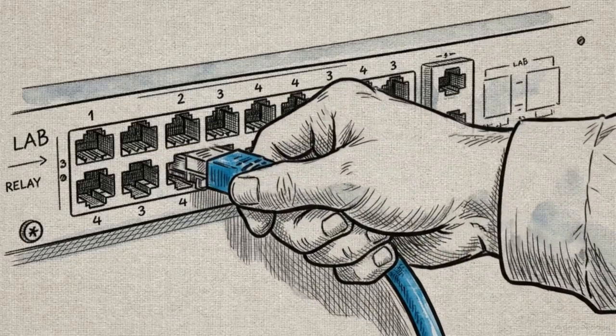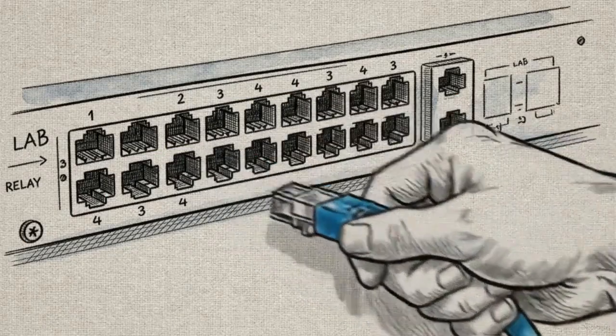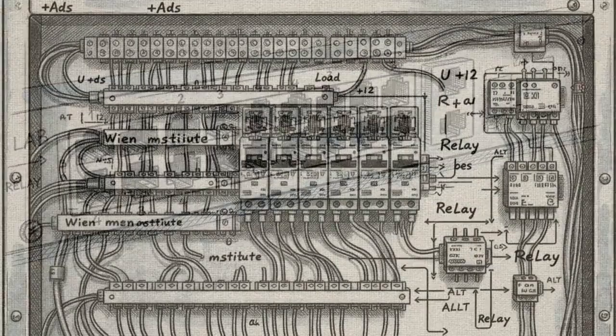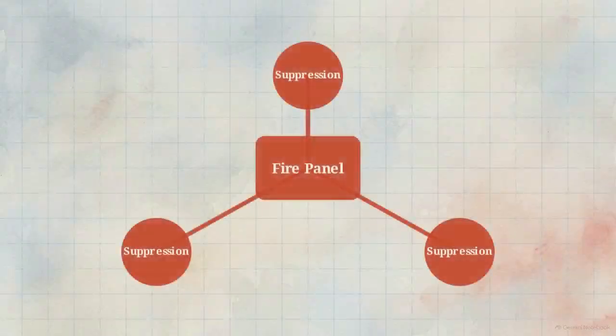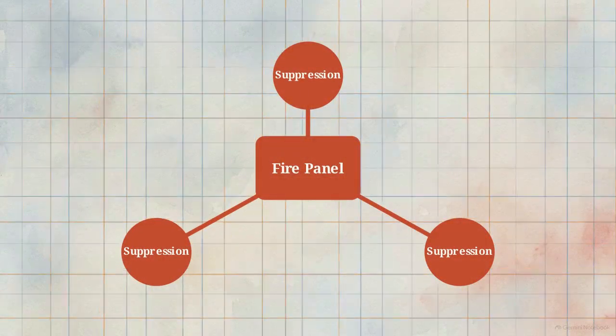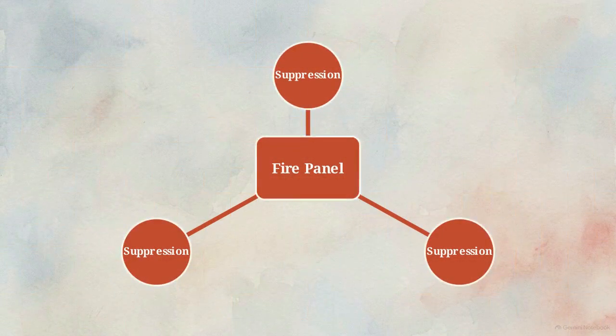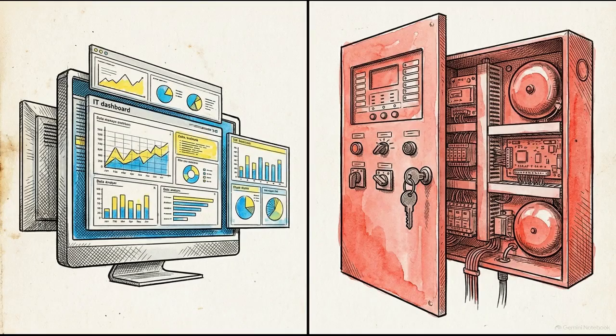If a network switch fails or a technician accidentally pulls an Ethernet cable during routine maintenance, a software-based release system would be completely blinded. Hardwired panels guarantee the signal reaches the suppression system regardless of IT network status. Situational awareness gives operators the data they need to investigate. But physical life safety interventions must remain hardwired, isolated, and immune to network vulnerabilities.